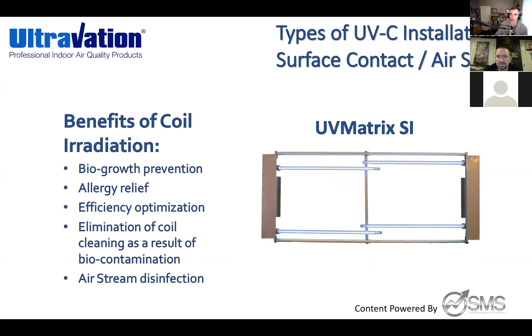We will adjust these bulb distances depending on what the customer wants. Standard is like a 70 to 80% disinfection rate, and that's what racks like this look like. But if this person's trying to gain a 90+% disinfection rate out of their commercial solution, we may adjust the bulb distance from top to bottom to get them closer together. As the bulbs get closer together, you're really tightening your field. We may have to add more racks of bulbs to help cover that. It really depends on the job, how big the coil is, and what their disinfection goal is.